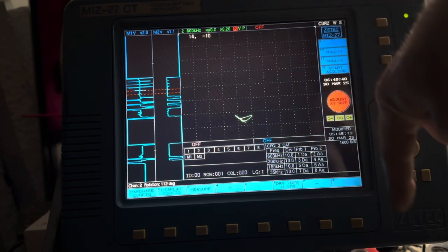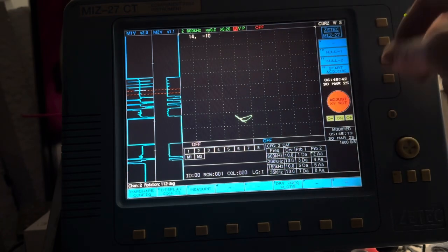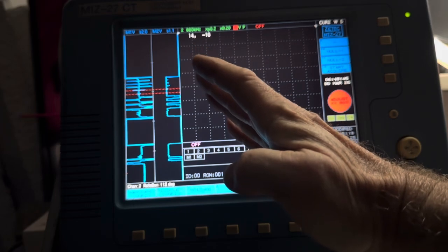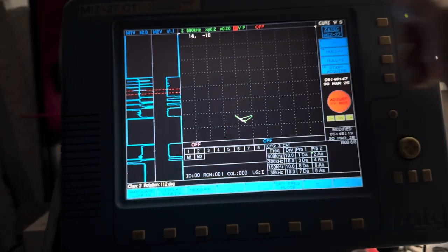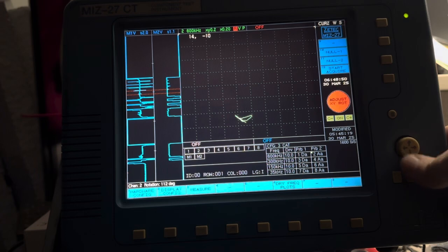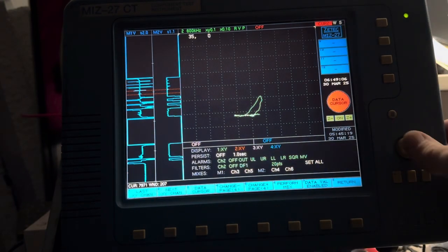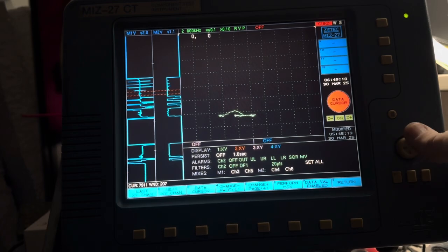But what you do during actual data evaluation is, rather than keep that impedance plane like it shows in the book, we change that liftoff line to occur more horizontal. Okay, that's the first thing. We set noise horizontal. Now, as I take my cursor and scroll up through the data, first of all, right there, that's probe wobble.